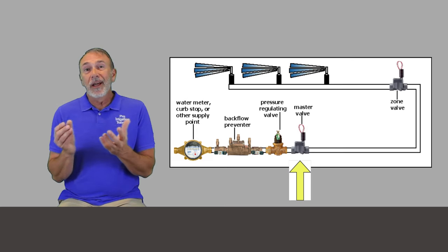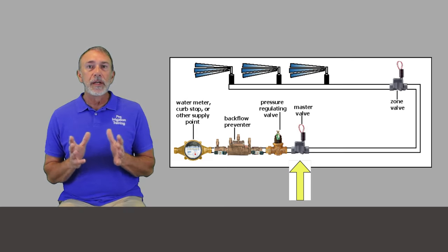So a lot of times when the system is running, that little tiny leak is not even going to be leaking anyway. And so as a repair technician to go in and work on systems that don't have master valves, sometimes I'll put one on there. If we can't find the leak or it's so small, but we know we're losing water.